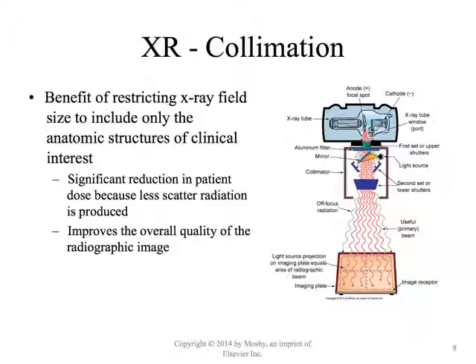Related to that is the collimation. In X-ray, we can reduce exposure to both the patient and ourselves by collimating appropriately. Now, there are a lot of facilities out there who ask us to open the collimators all the way, and sometimes that might be appropriate, but there are a lot of other times when we might want to collimate a little bit more. One thing to bear in mind with collimation is we don't want to over-collimate, especially if we're using a digital system, because that can throw the machine off. But on the whole, collimation will result in a significant reduction of dose to the patient as well as better pictures.